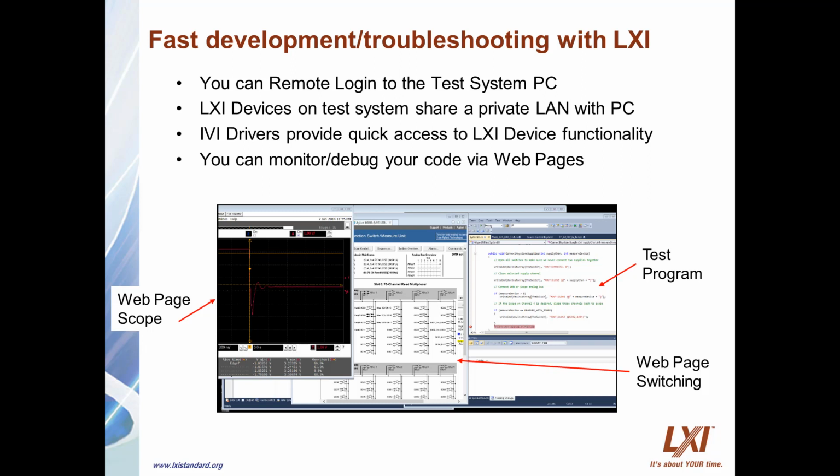The IVI drivers that come standard with an LXI device provide quick and easy access to the device's functionality. And with web page monitoring and control, you can figure out what's going wrong in your test system simply by pausing your program, looking at a web page showing the signal, for example on a scope, and then analyzing the web page associated with switching to find out you closed the wrong switch.